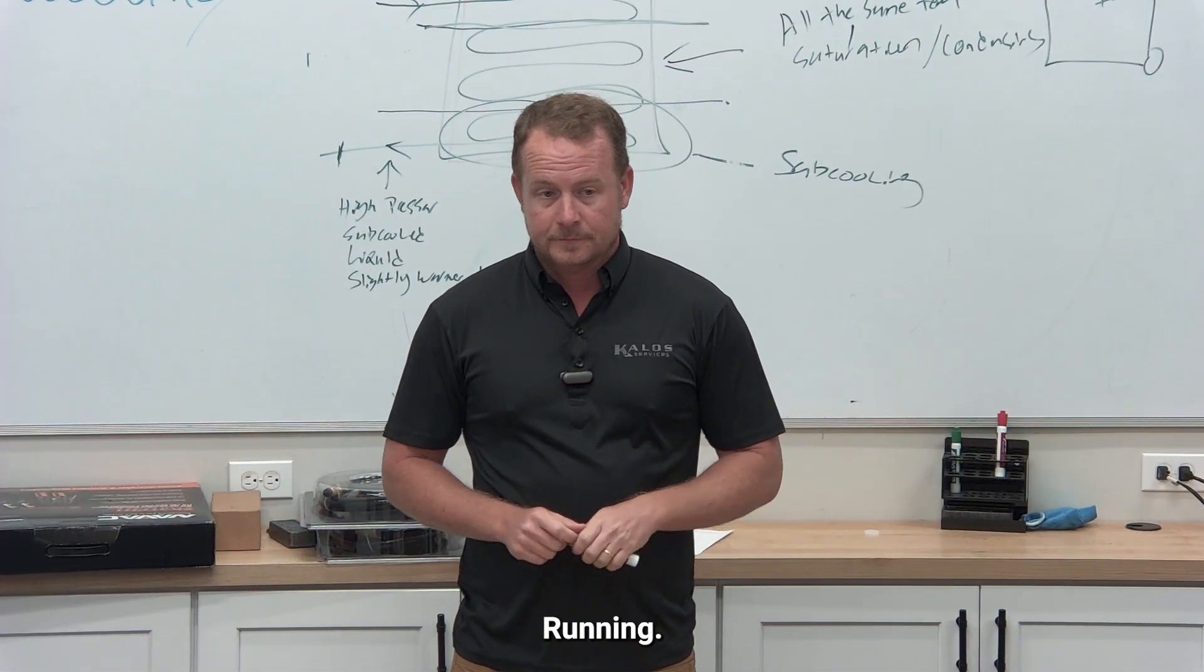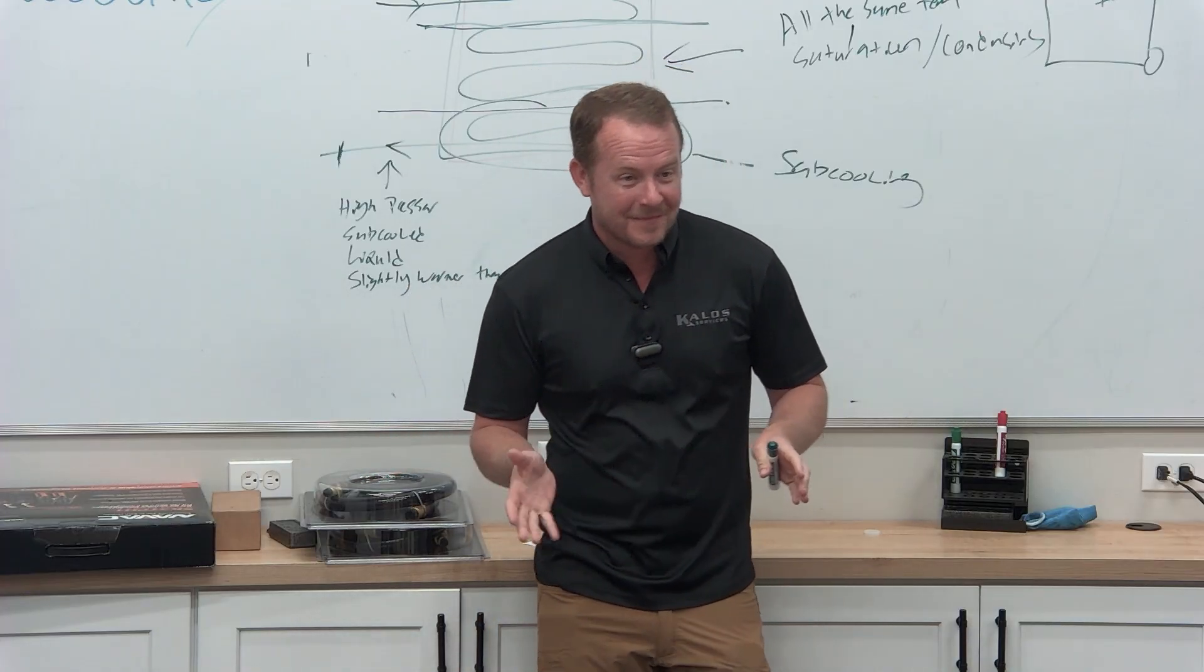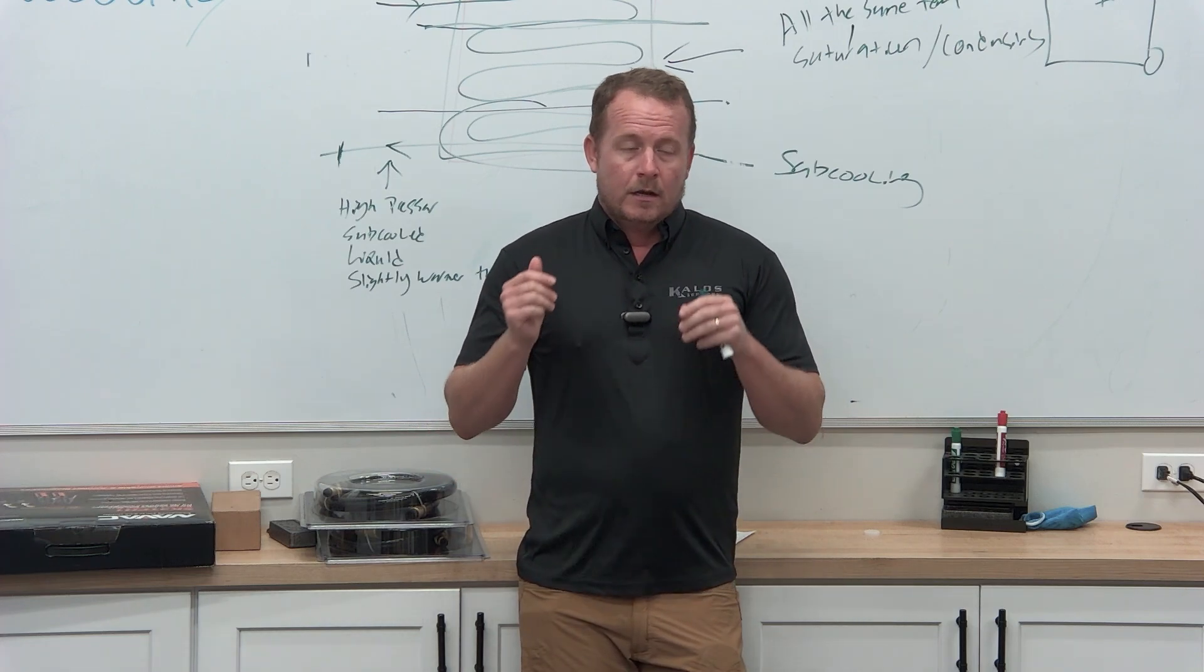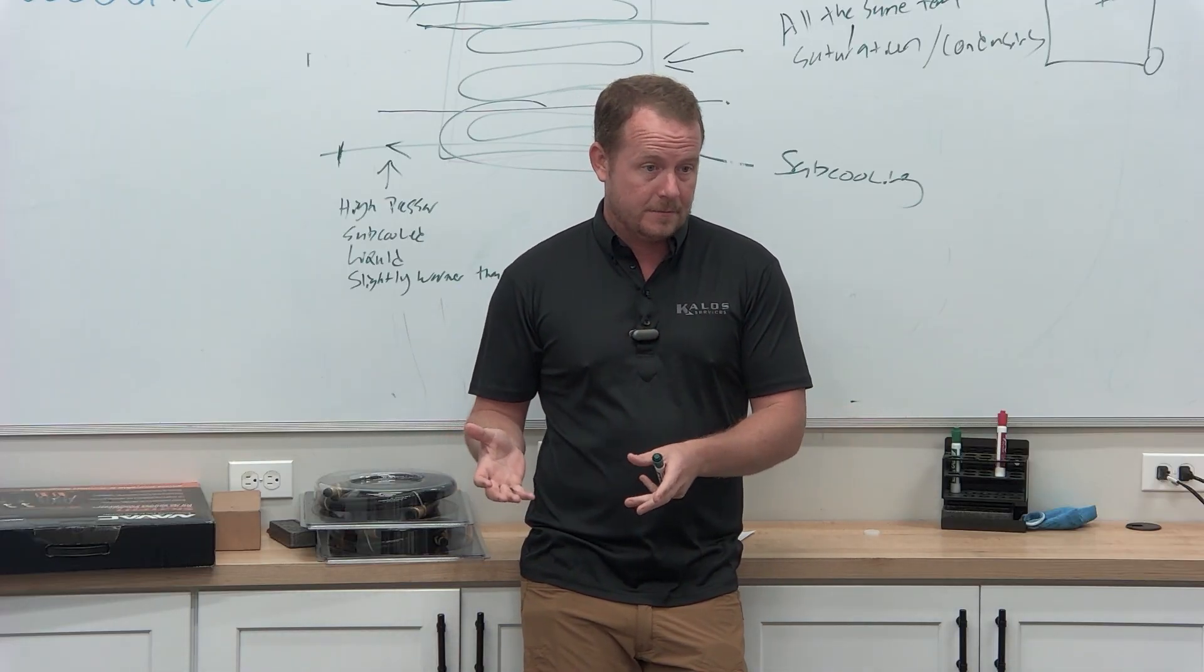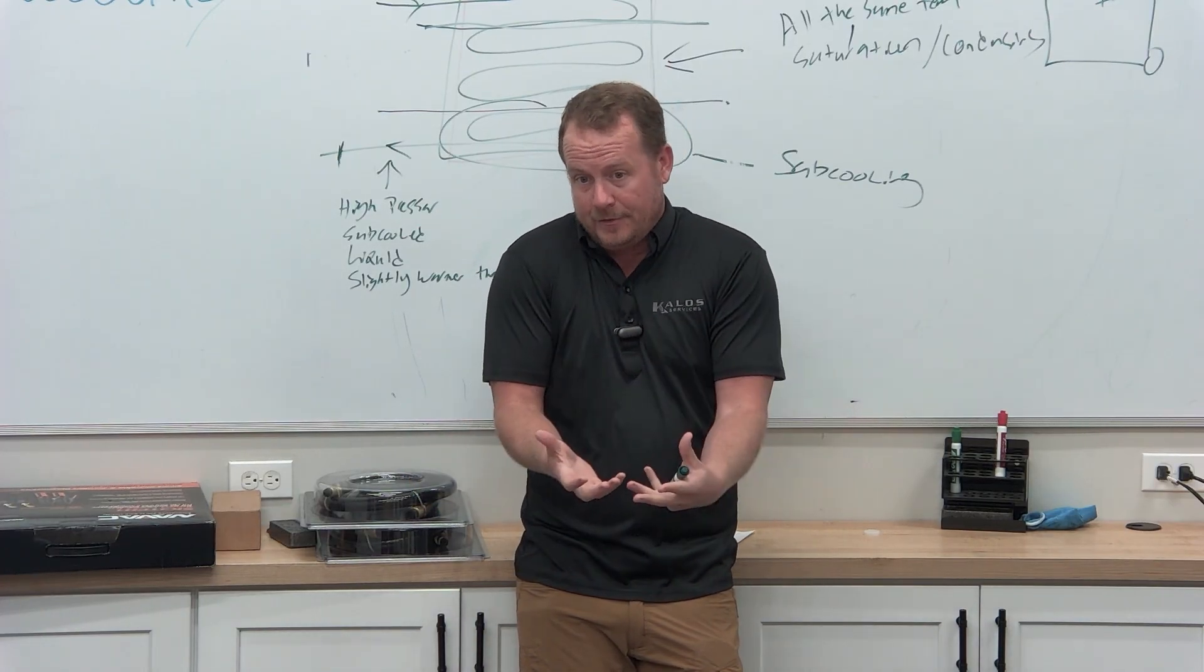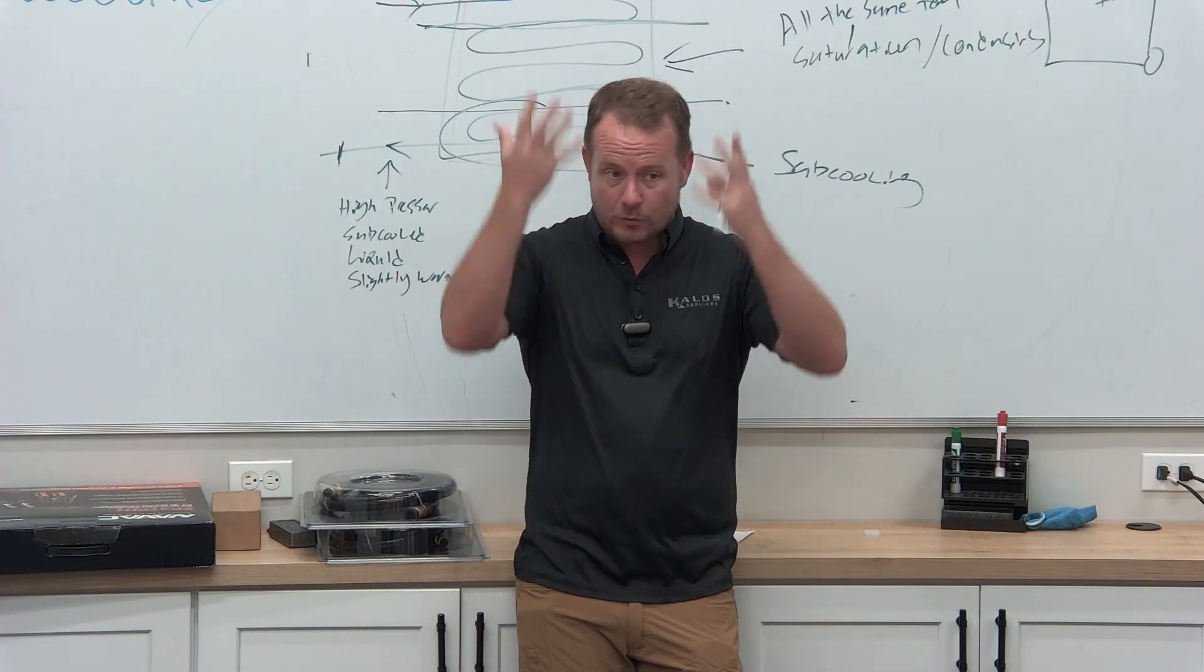When do crankcase heaters, when are they supposed to run? When do they operate? Do they operate when the compressor is running or the compressor is not running? Actually, when it's not running, because if it's running, the compressor is already hot. All the crankcase heater is doing, I mean, it's right in the name. All it's doing is heating the crankcase. When a compressor is running, the crankcase is already going to be warm. So what a crankcase heater's purpose is, is to keep the compressor warm so that refrigerant doesn't condense in the compressor. If refrigerant condenses in the compressor, you get flooded start. You get that same effect of putting liquid refrigerant in the suction line. Liquid refrigerant goes and just sits in there, gathers in the bottom of the compressor when it's off for a while. Then when it starts up, boom, it boils immediately, and it just throws the oil all out of the compressor.